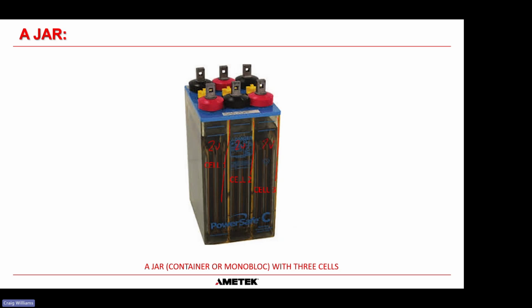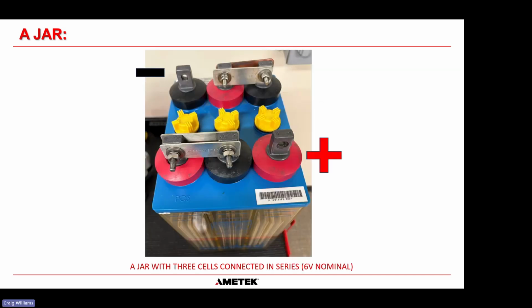So this system has to be connected in a specific way. The negative has to be connected to the positive of the next one, and this negative would have to be connected to the positive of this one here. Then you would have your main cable coming in here and your main cable coming out here. If that's the main positive and that's the main negative, this would be a 6-volt monoblock that has 3 cells inside it. That's what it looks like - a jar with 3 cells connected in series. It would give you 6 volts nominal when they're connected together the way that they should be.